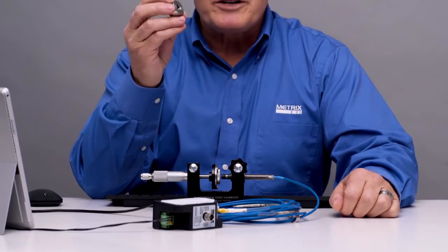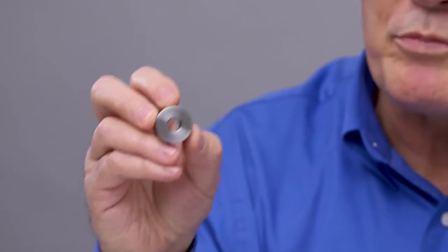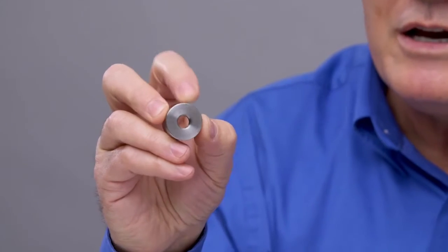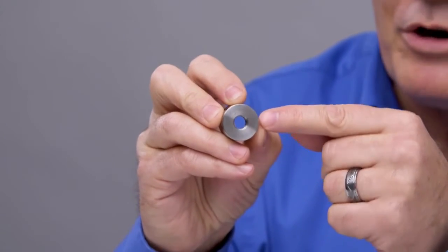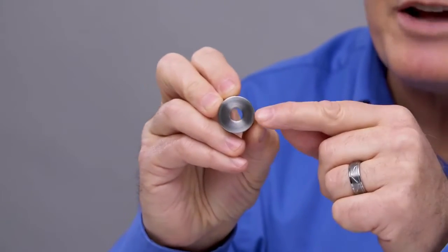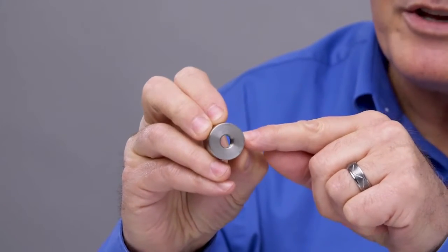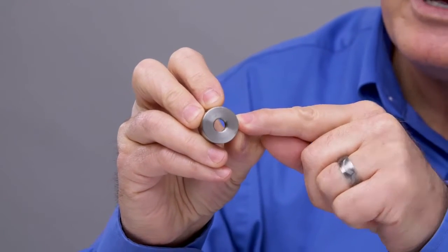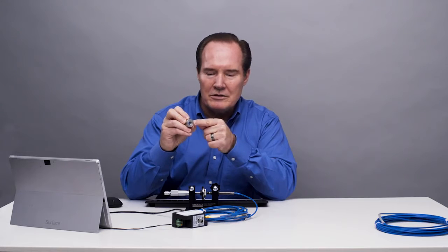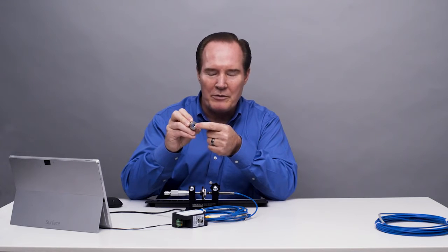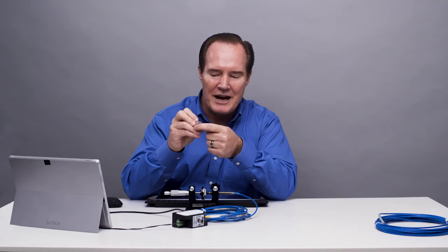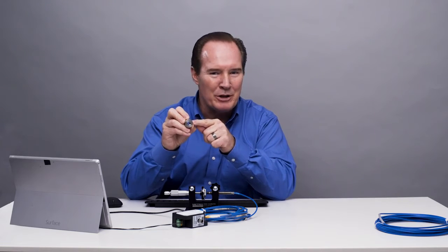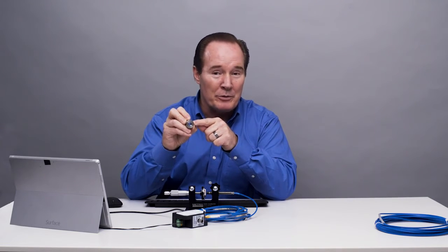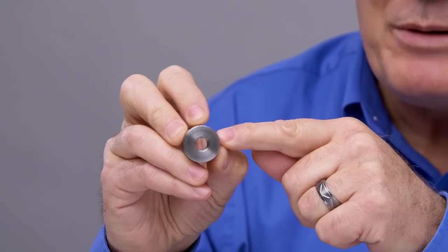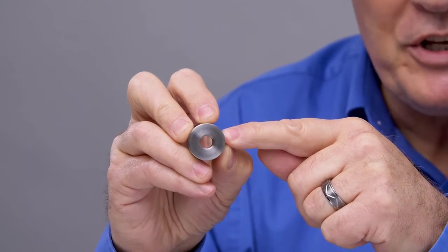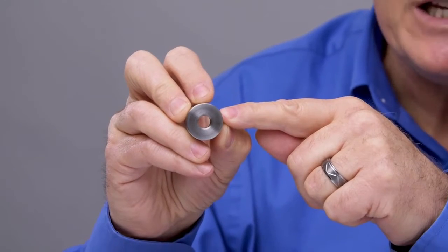In a normal proximity probe system, you want to be at least one probe tip diameter away from the probe tip in order not to have any interference. So this outside diameter on this metal disc I have, you can't have any metal close to that probe tip that will be right there. So you want to be outside that circle. So it's at least 19 millimeters or 25 millimeters with some competitive probes. But the Metrix beam is actually pretty narrow already, so we need 19.